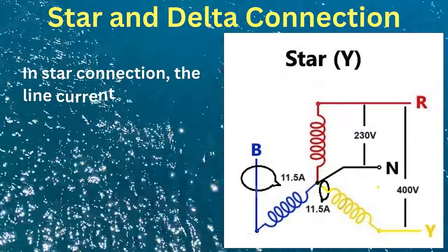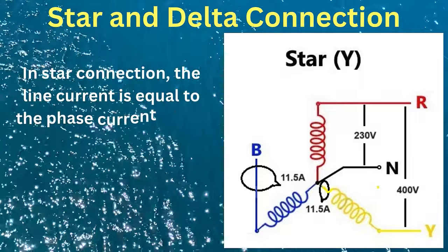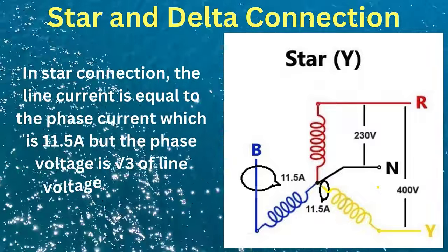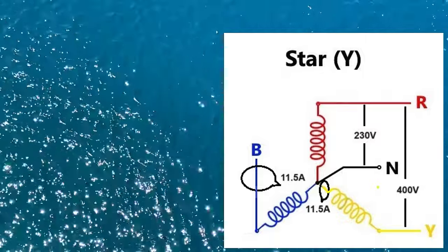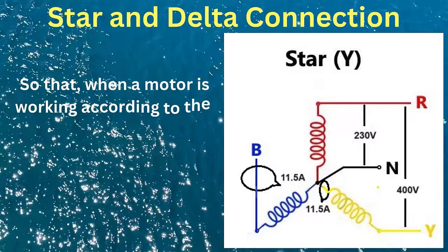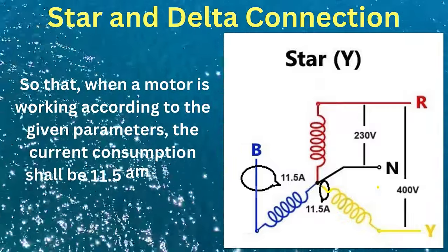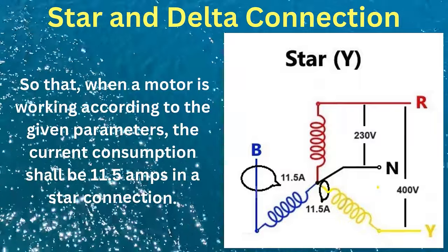In a star connection, the line current is equal to the phase current, which is 11.5 amps, and the phase voltage is the line voltage divided by root three — that is 400 volts divided by root three, equals 230 volts. So when a motor is working in a star connection according to these parameters, the current consumption will be 11.5 amps.